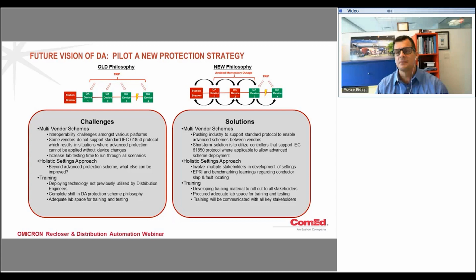So we are pushing the industry to support standard protocol to enable these schemes between multi-vendors. But for the short-term solution, we're trying to utilize controllers that support IEC 61850 protocol, where applicable, to allow for scheme deployments. Next, our holistic settings approach. So beyond our advanced protection scheme, what else can be improved? In order to do this, we're involving multiple stakeholders in the development of the actual settings, and we're benchmarking learnings from EPRI regarding conductor slap and fault locating.